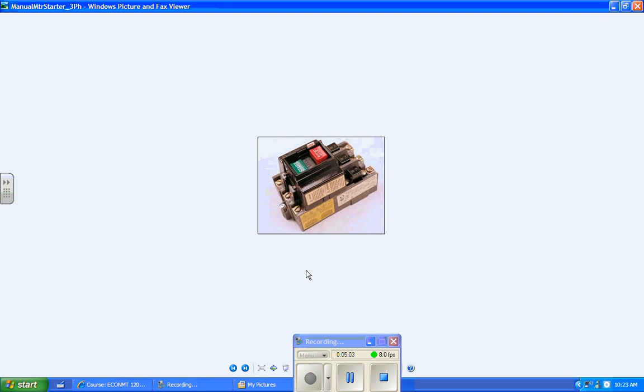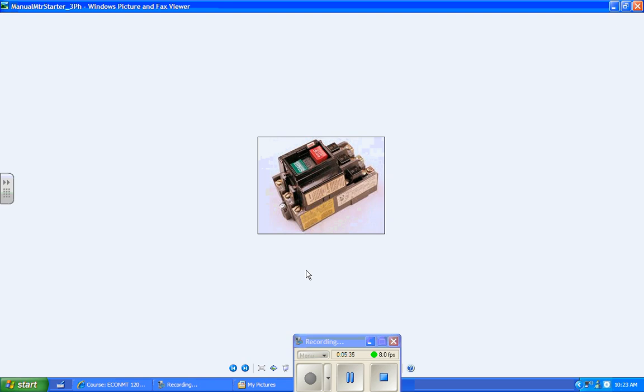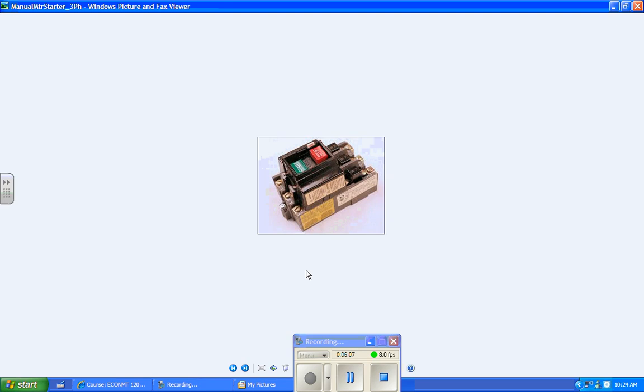Look at the big drawing at the lower half of page 37, and you'll see a magnetic thermal overload. It's not magnetic, but it's operating a magnetic coil. See the normally closed contact at the bottom? It's spring loaded to move up and down. When the little wheel turns and allows it to go up, it opens a circuit and releases the magnetic coil. The overloads in a manual motor starter are identical to this, except instead of having electrical contacts down at the bottom, the little arm has another bar going up and all it does is hit the release latch of the locking latch of a manual motor starter. The magnetic type opens a circuit, and the manual type pushes the latch open and lets the springs take over and open the circuit of all three power circuits.